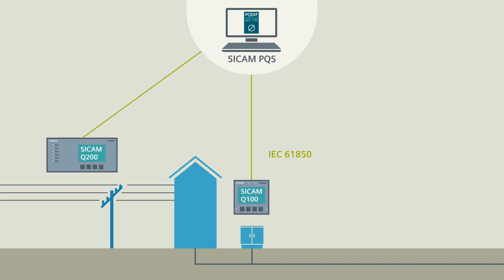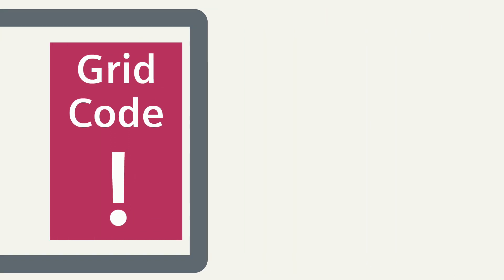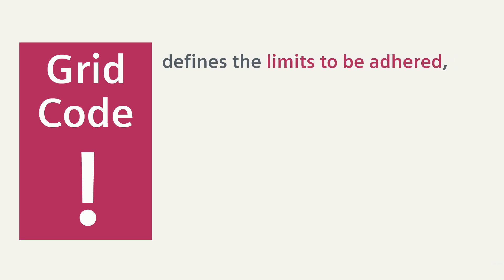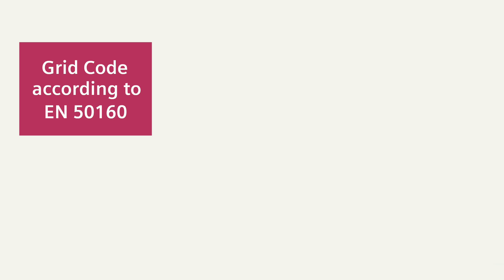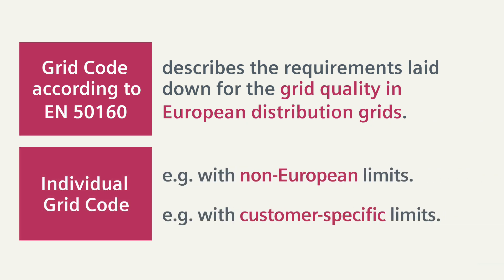SICAM PQS enables all power quality data from the field level to be centrally gathered and archived for a multitude of connected SICAM power quality devices. SICAM PQS subsequently assesses the gathered data on the basis of grid codes. A grid code defines the limits to be adhered to for all measured quantities, like the maximum permissible level of harmonic oscillations. The grid code defined by the EN 50160 standard describes the requirements laid down for grid quality in European distribution grids. You can also define your own grid codes for applications with individual quality requirements.